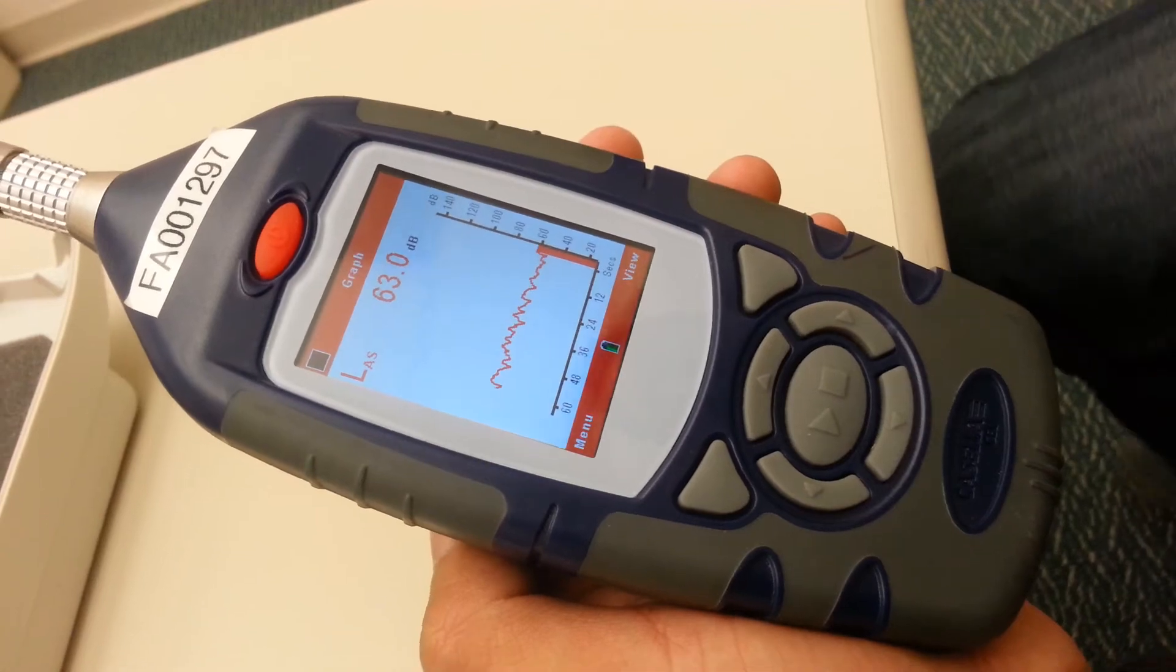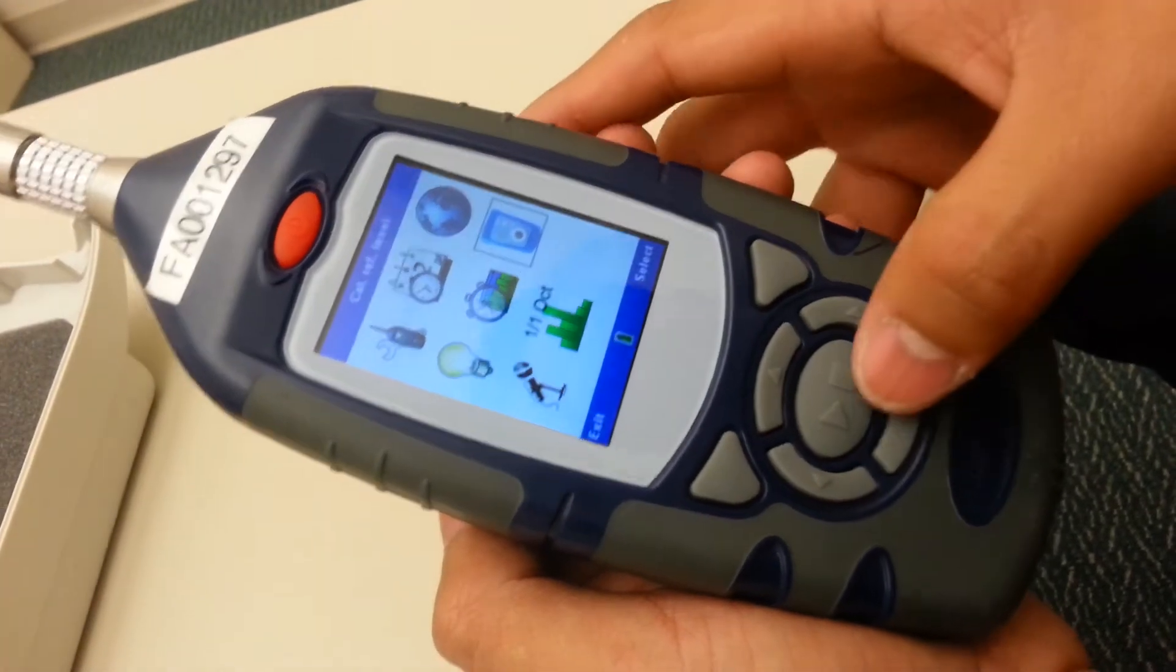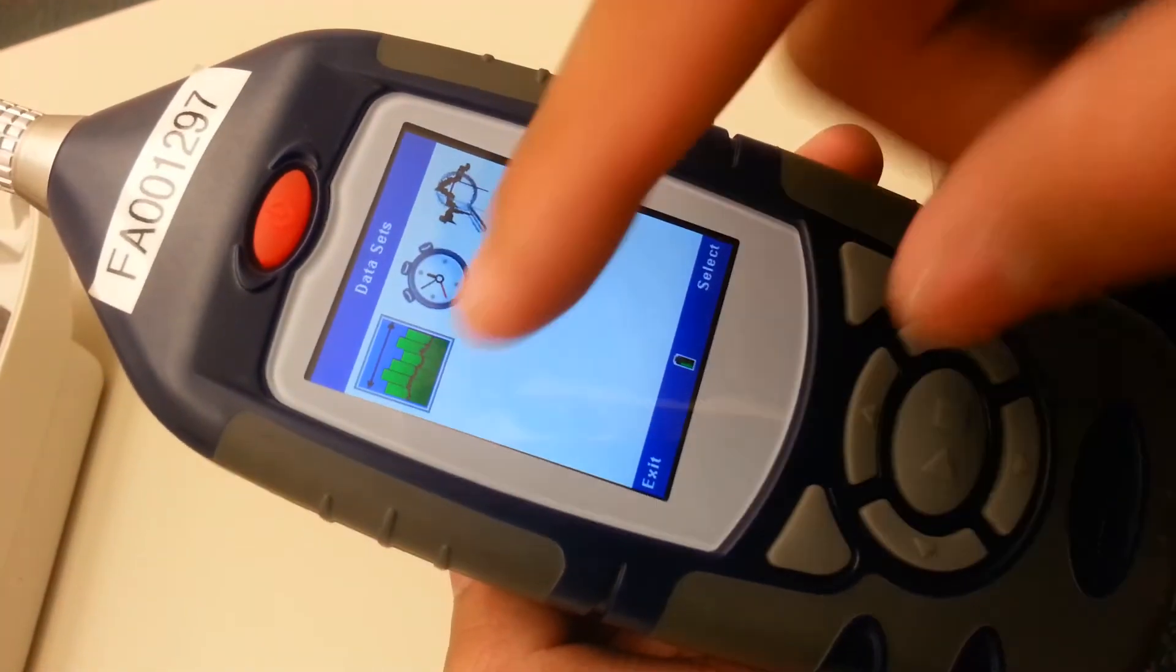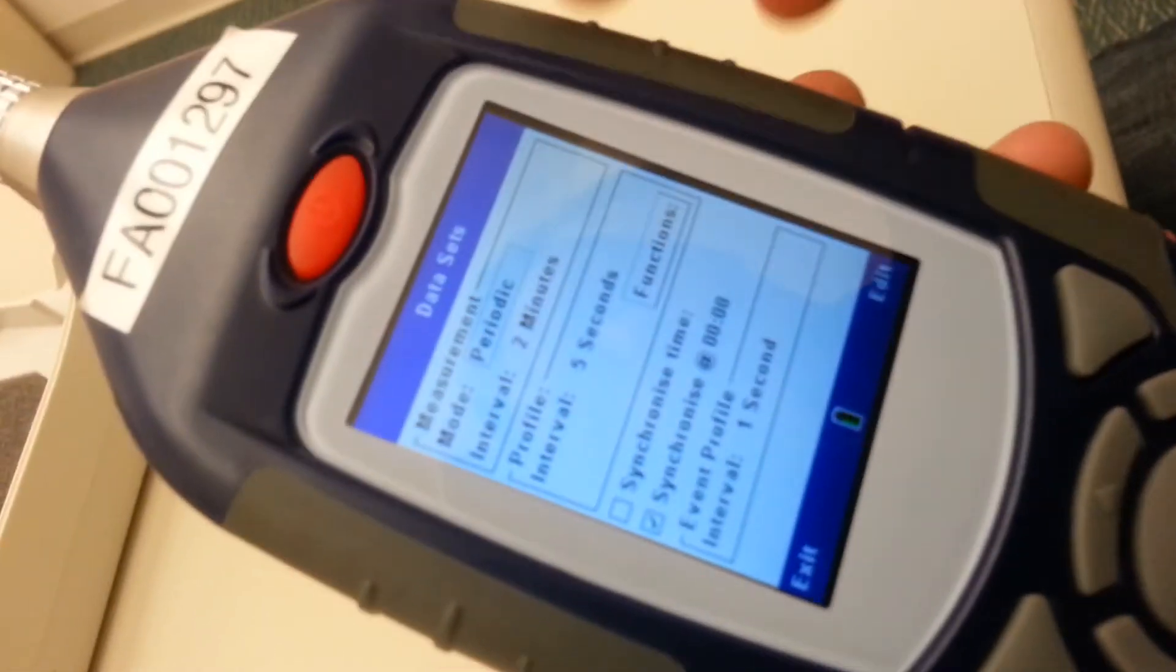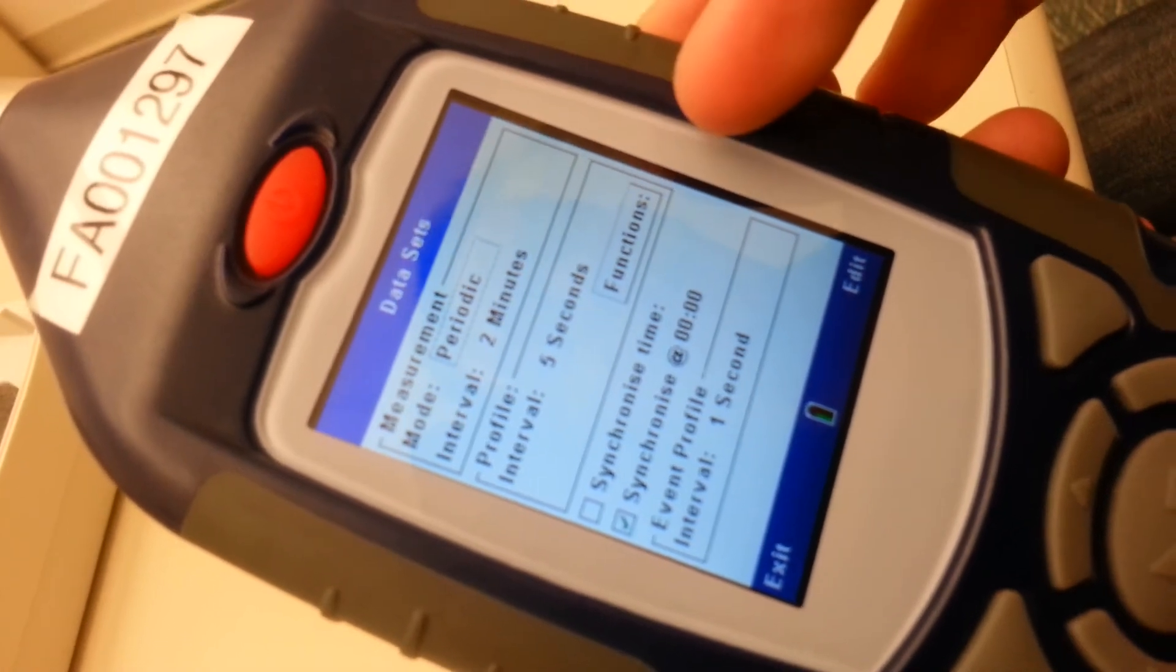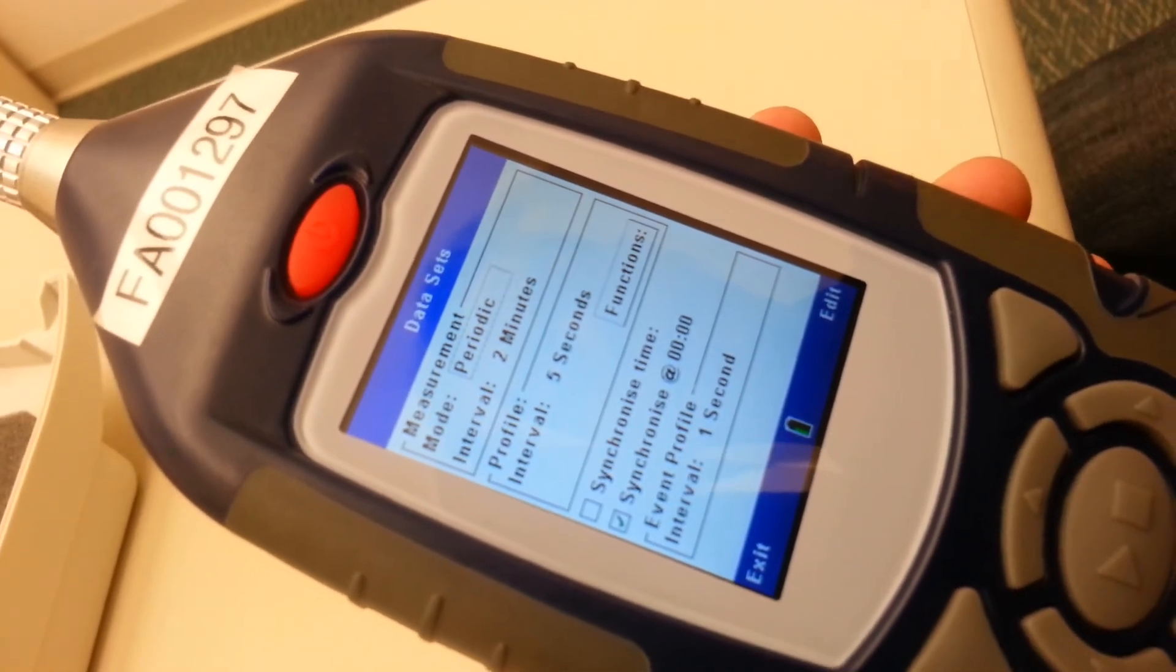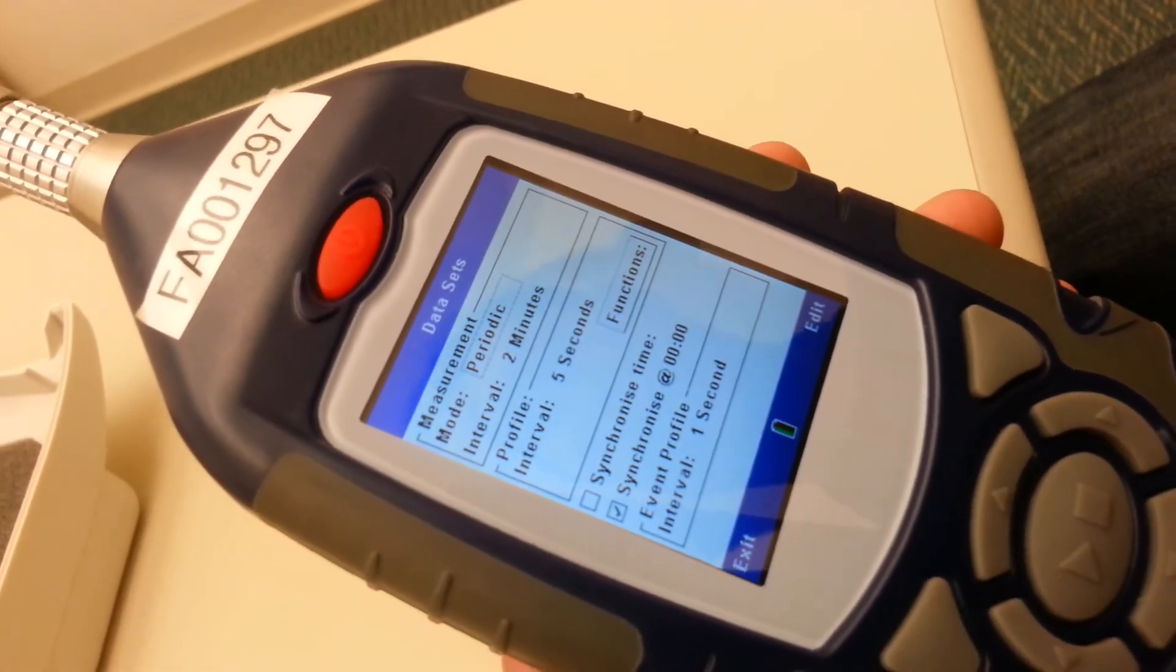One thing you might need to change when you first get the sound level meter is you go to menu, go to settings, and then go to the middle. Measurement control. You can select here and then select the first icon which is data sets. It should be set at periodic, at two minute intervals, and at profile at five seconds. Sometimes the intervals for the periodic measurement screen will be one minute or five minute. Let's set it at two minutes so you can get a data point at each two minute.